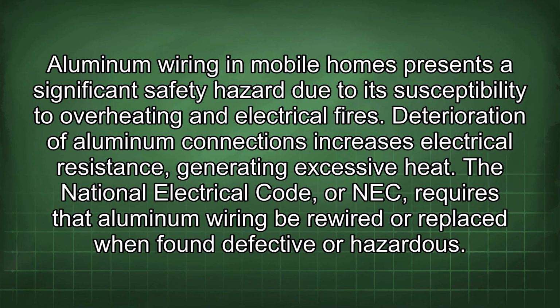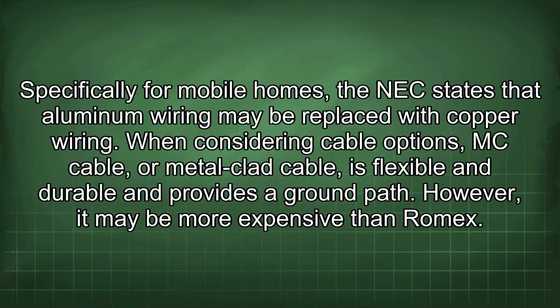Aluminum wiring in mobile homes presents a significant safety hazard due to its susceptibility to overheating and electrical fires. Deterioration of aluminum connections increases electrical resistance, generating excessive heat. The National Electrical Code, or NEC, requires that aluminum wiring be rewired or replaced when found defective or hazardous. Specifically for mobile homes, the NEC states that aluminum wiring may be replaced with copper wiring.